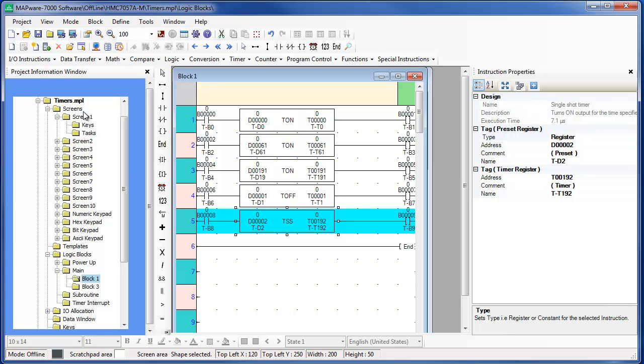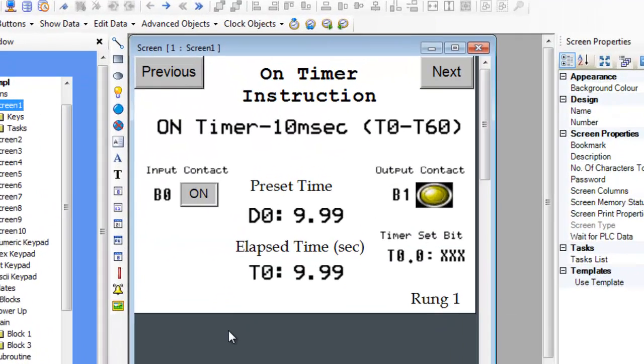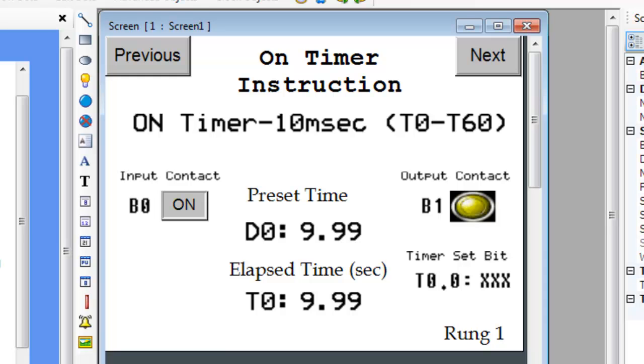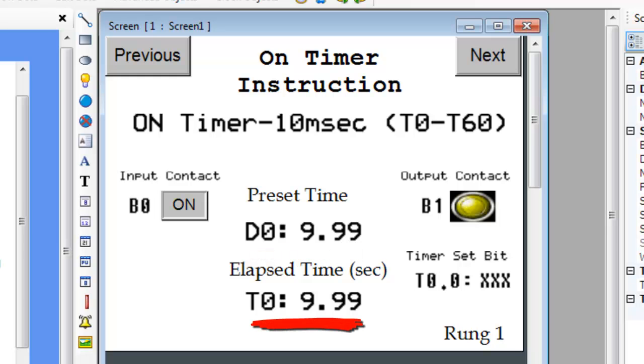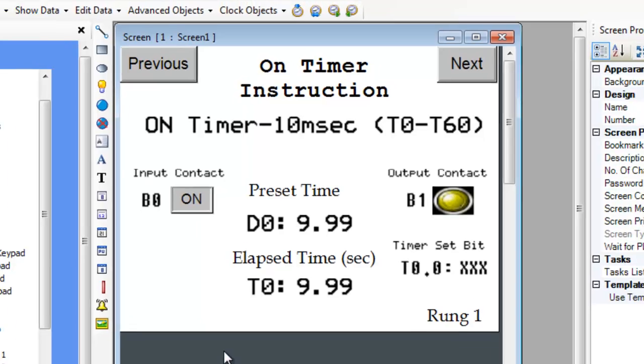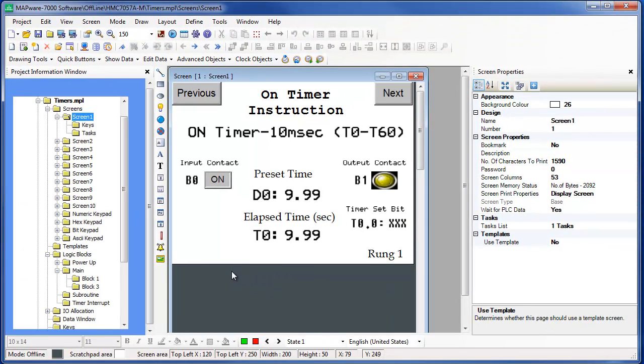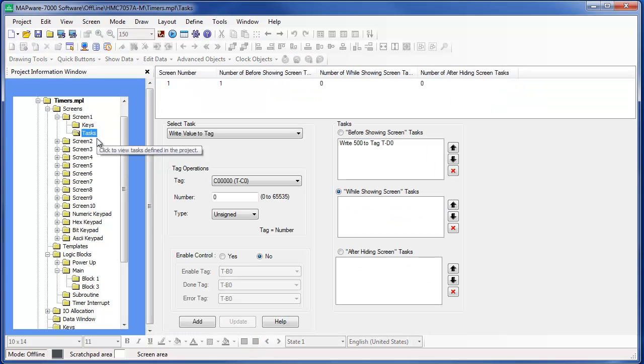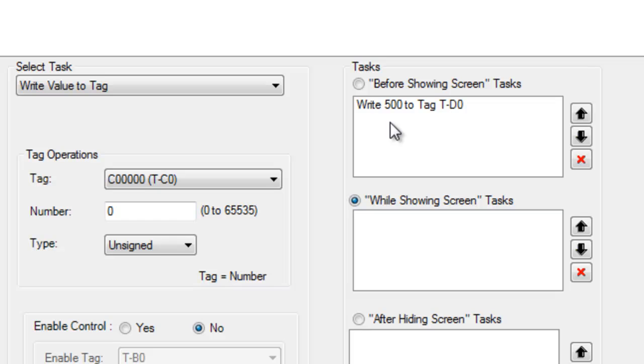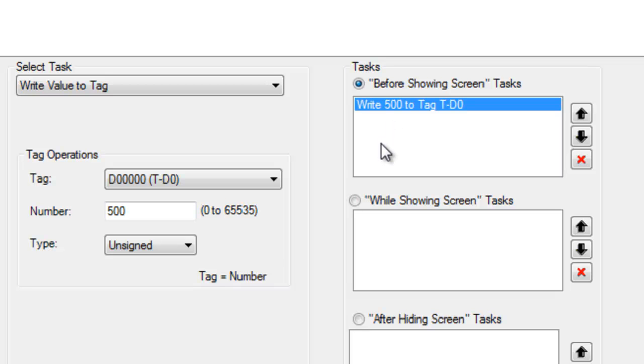Let's create some screens to demonstrate each timer. Screen 1 demonstrates the operation of the 10 millisecond on timer in rung 1. The timer will start when the B0 toggle bit is pressed. Register D0 is used to place a preset value and we will monitor timer T0 as it counts. Output B1 and timer set bit T0 should turn on once timer T0 reaches the value in preset D0. We want the timer to count for 5 seconds, so in the task folder for screen 1, we preload D0 with 500 whenever the screen opens. Since 10 millisecond timers increment every hundredth of a second, a value of 500 gives a 5 second count.